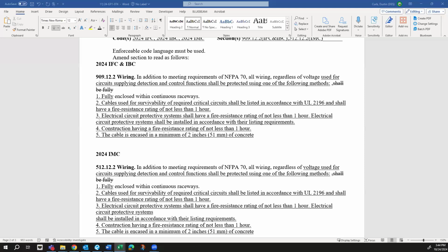So I'm going to run a scenario here. For example, option number 4, which says construction having a fire resistance rating of not less than 1 hour. So technically, if you have a stacked electrical room rated for 1 hour, what that section says is you can have the cable run within that 1 hour stacked electrical room, like open cable without continuous raceway. And I'm thinking that might lessen the intent of the original requirement, where it would require continuous raceway anyway.